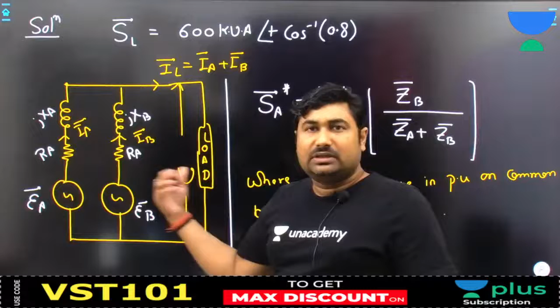If we have SA, we can calculate SB also. What is SB? Sir, the total load kVA is SL and the kVA shared by the two transformers. So if the kVA delivered by transformer A is known and load kVA is known, then we can calculate the kVA delivered by transformer B also. That will become SL minus SA. Is it okay? Yes, sir. So SB can be calculated in a simple fashion as SL minus SA. But keep in mind, this is a phasor sum. Don't do it directly, arithmetically. Okay. So you have to keep in mind that this is a phasor.